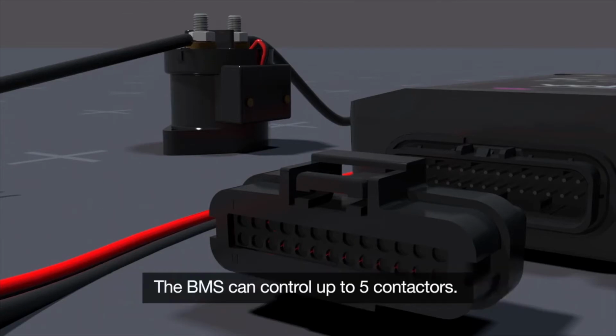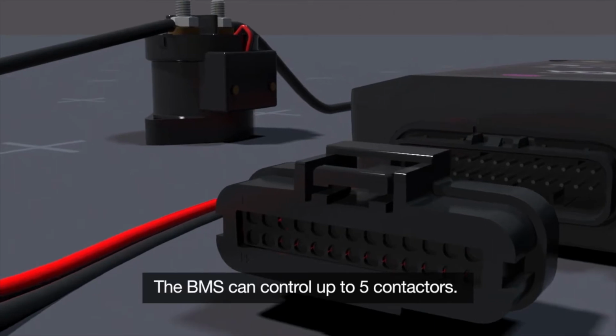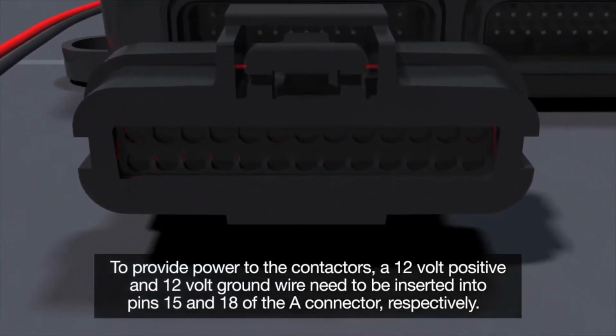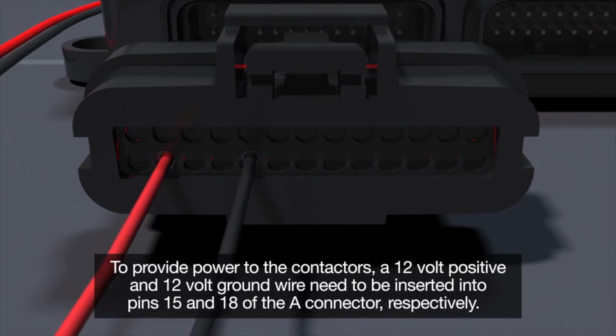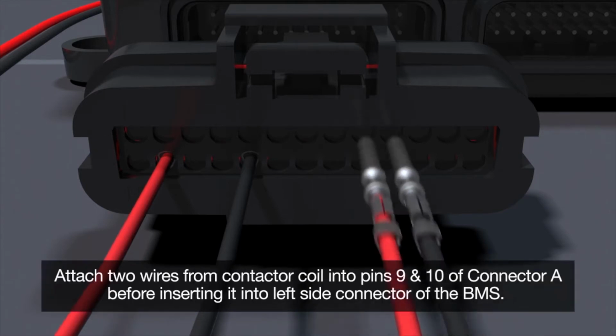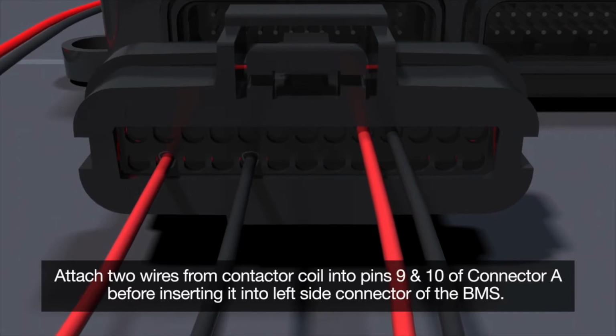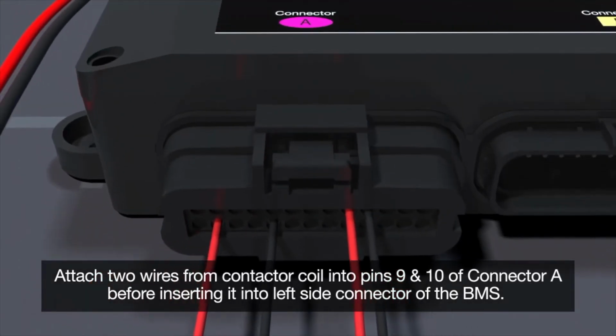The BMS can control up to 5 contactors. To provide power to the contactors, a 12-volt positive and 12-volt ground wire need to be inserted into pins 15 and 18 of the A connector, respectively. Attach 2 wires from the contactor coil into pins 9 and 10 of connector A before inserting it into the left side connector of the BMS.